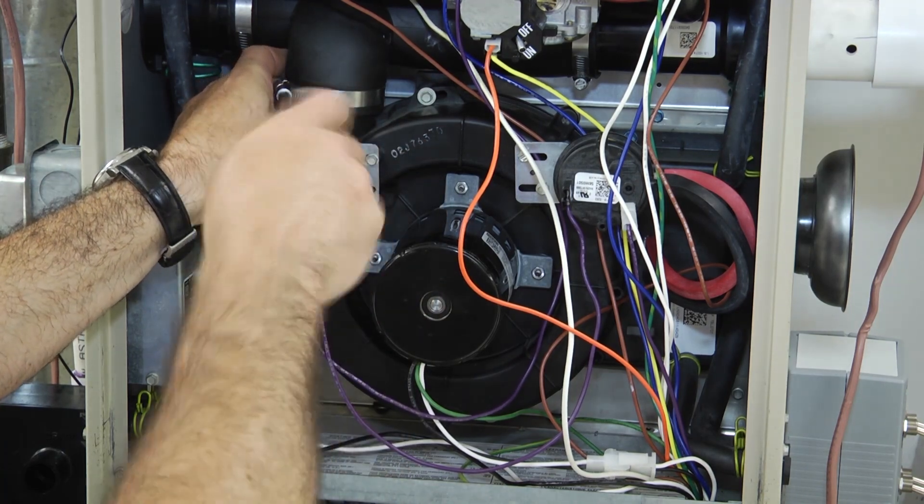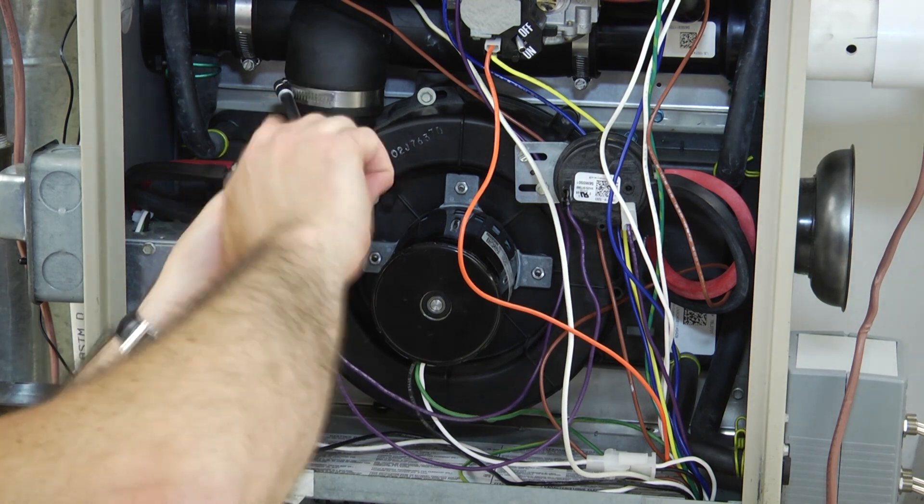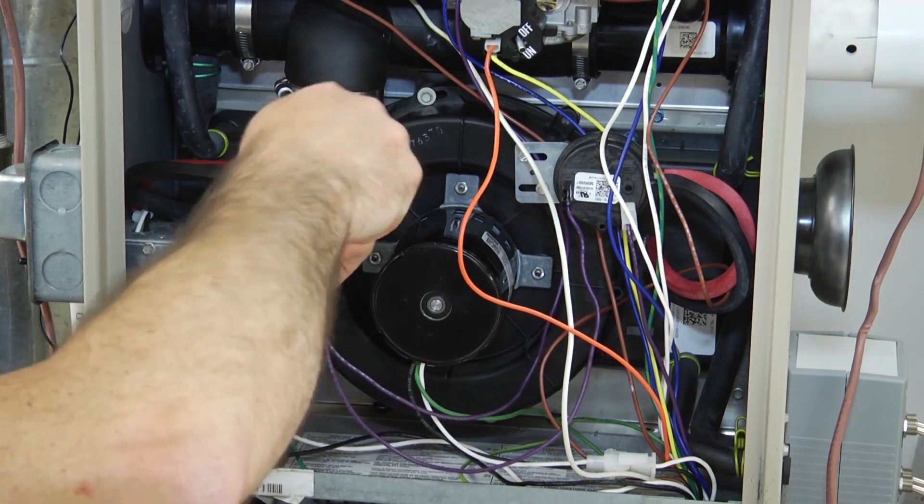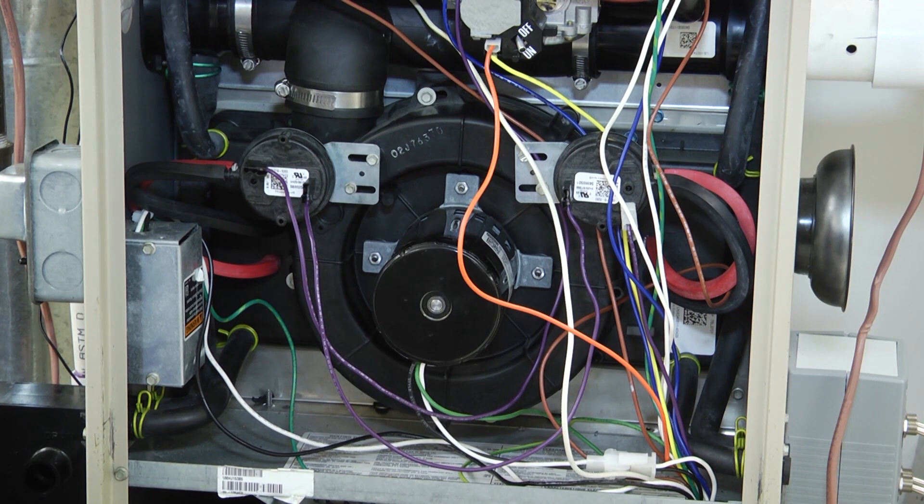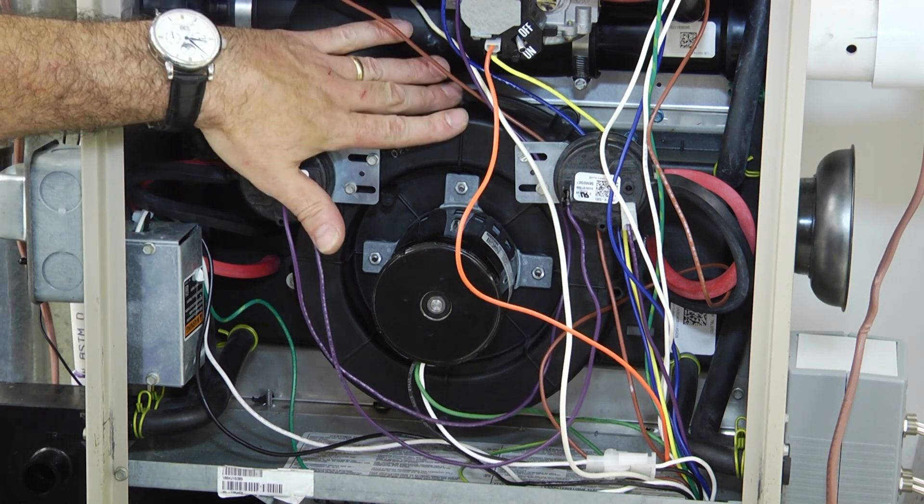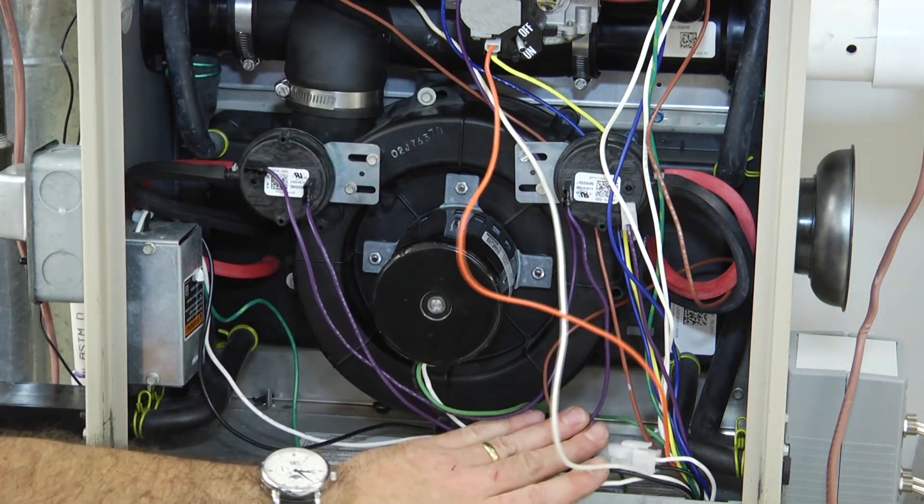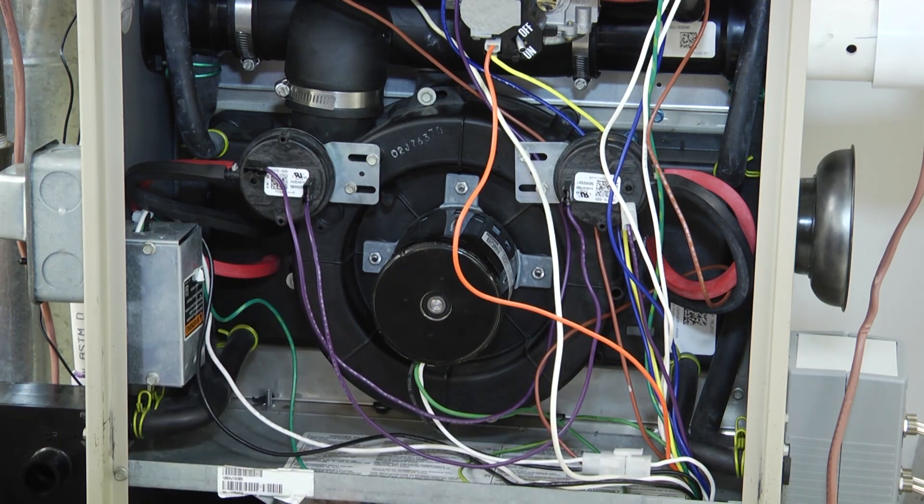If you don't get this thing nice and tight, what will happen is you'll get water coming out of it through the combustion process, and you'll have water all over the place. So again, make sure that your clamps run nice and tight. Your screws are back in place. You're all wired up and ready to go. That's it. You just replaced the venter motor.